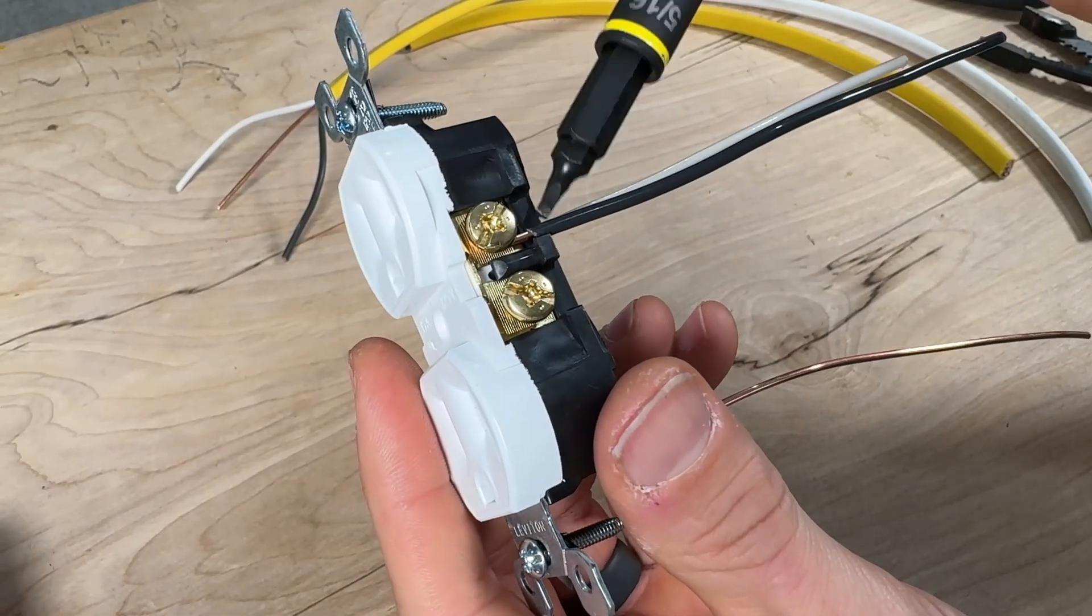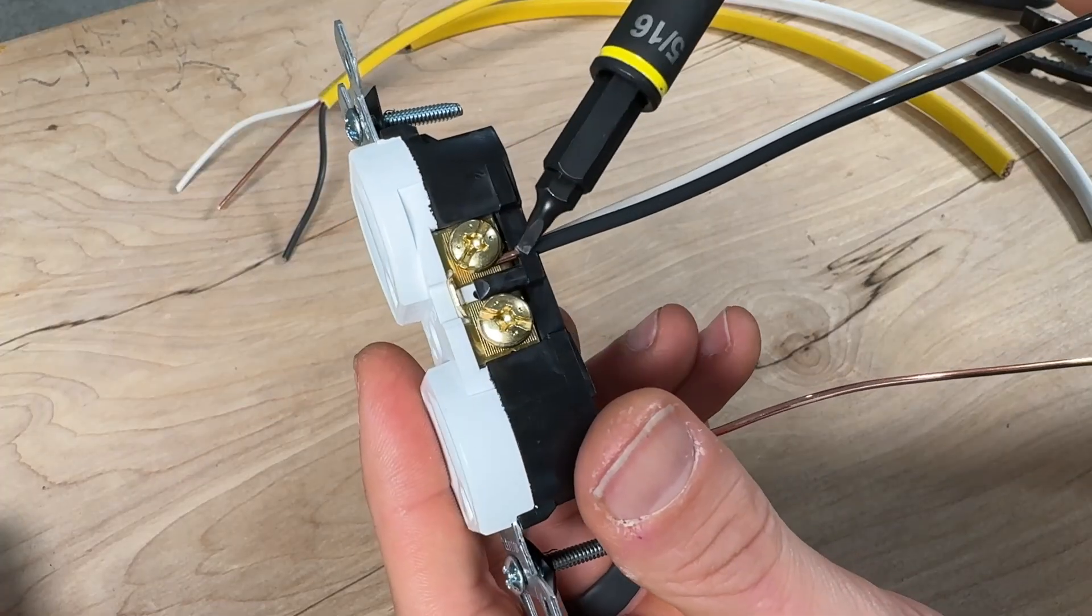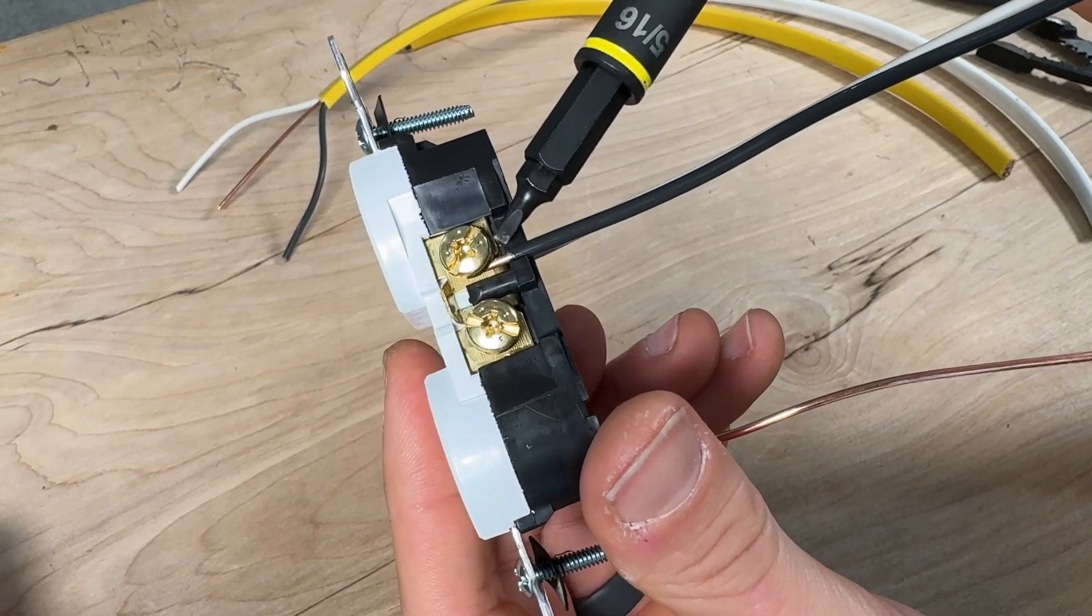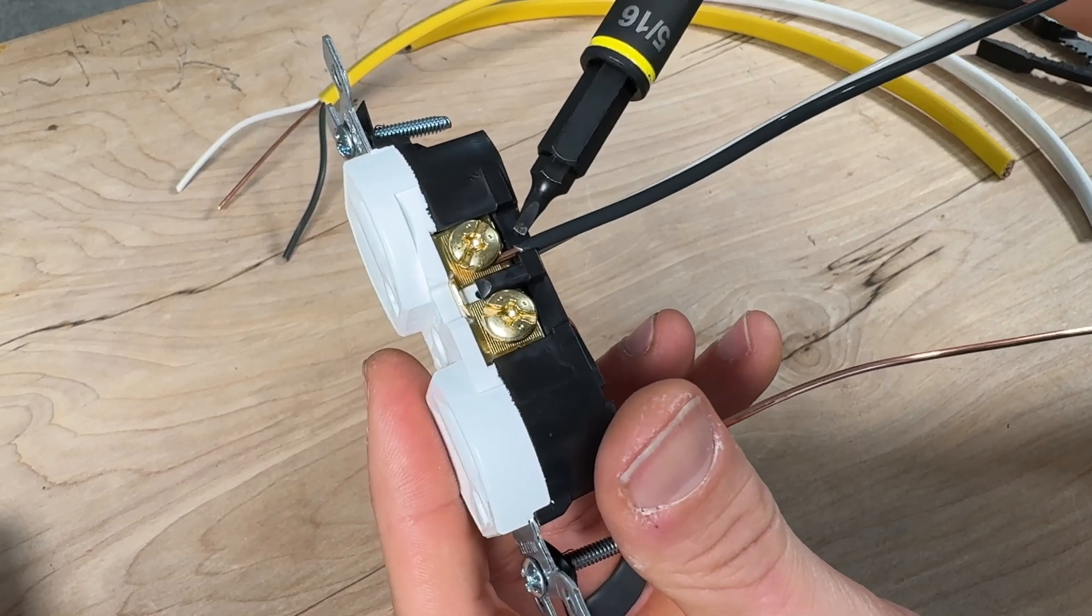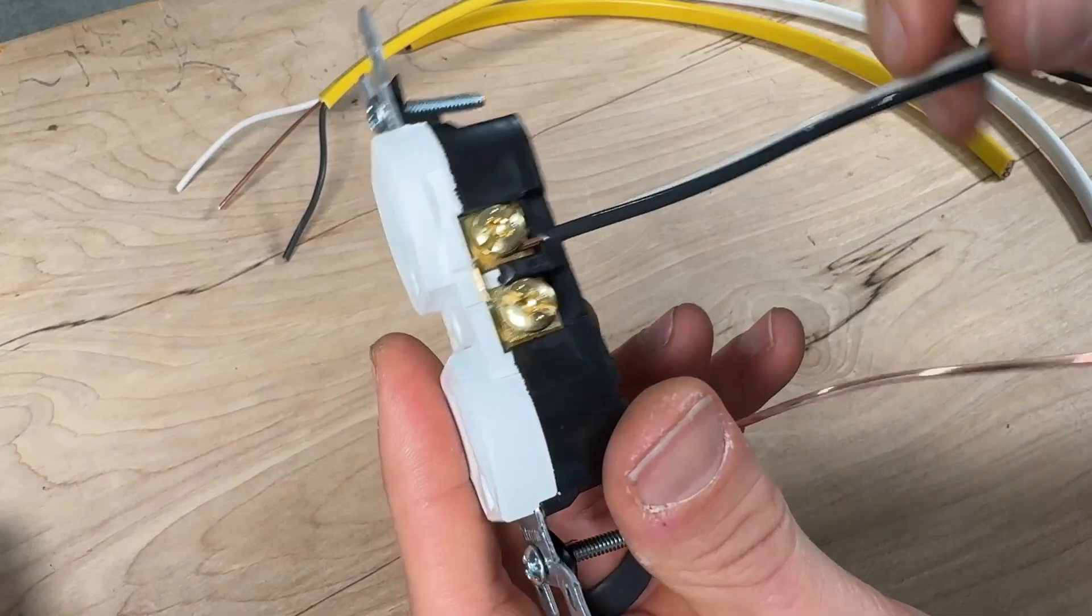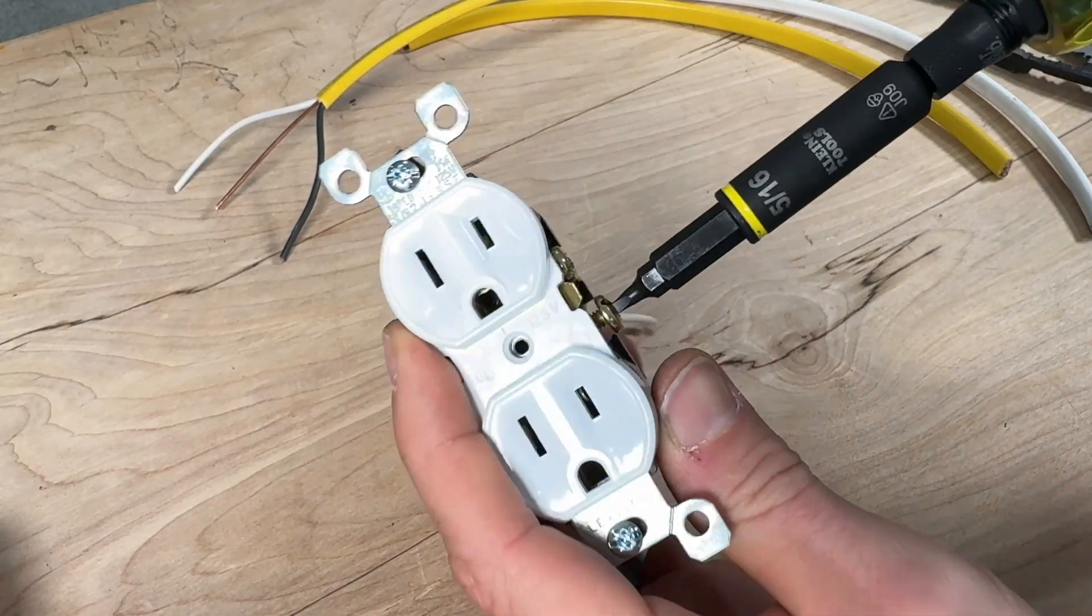This is what I would want to see. I want to make sure there's no insulation below the screw terminal that would separate the screw terminal from the actual copper. Also, I don't want to have the insulation stripped far enough back where I have exposed copper past the housing.